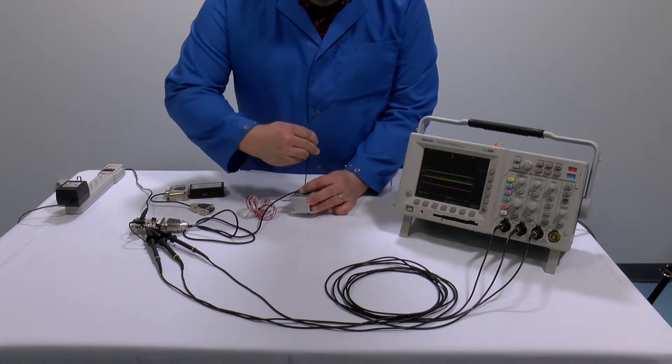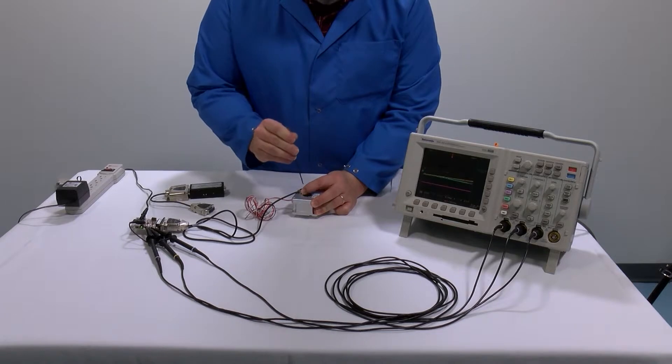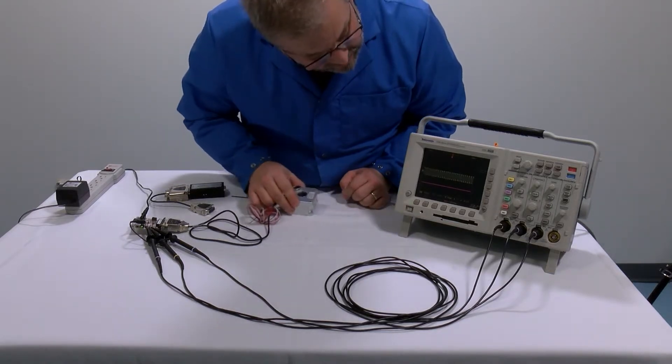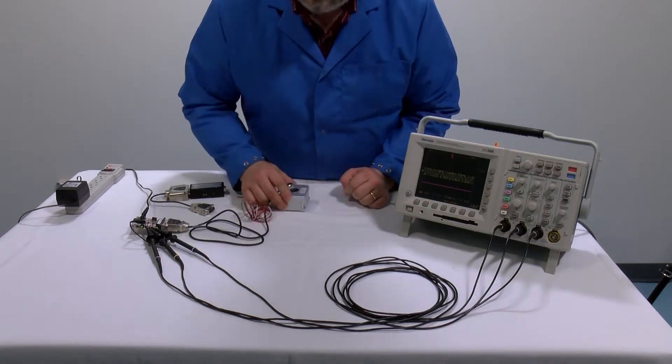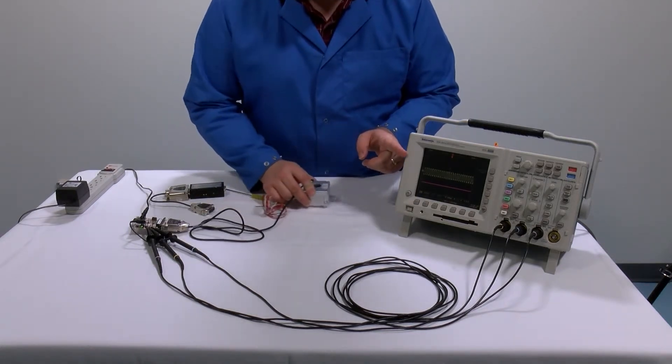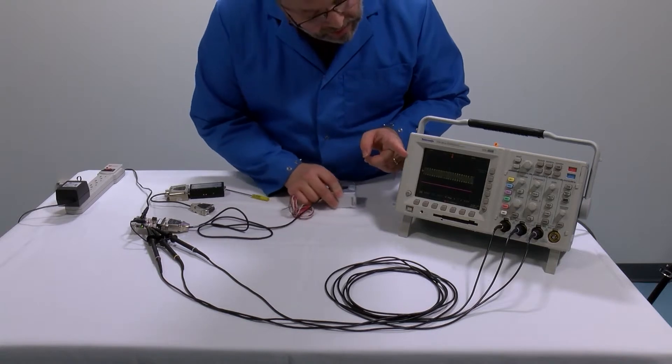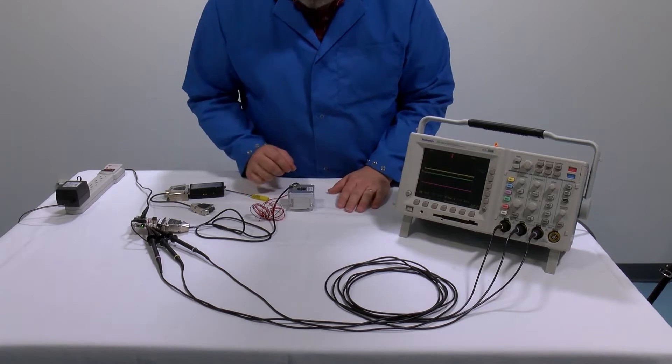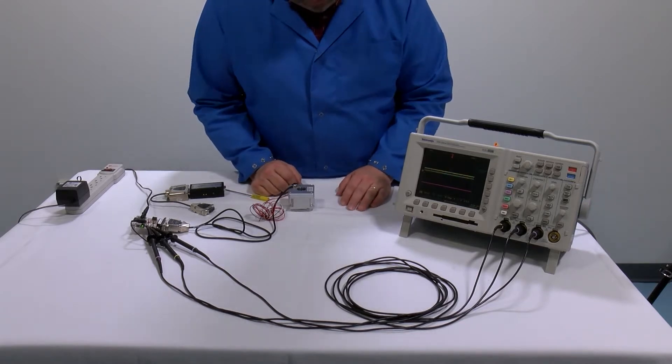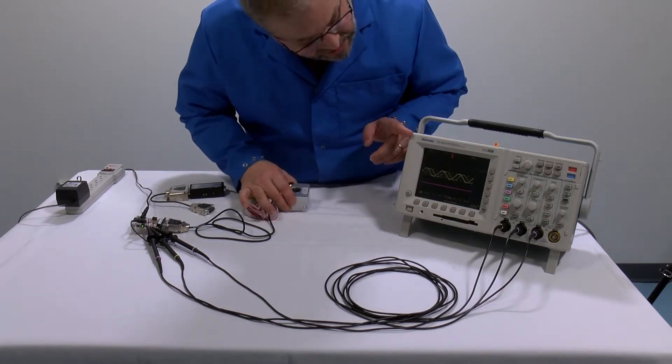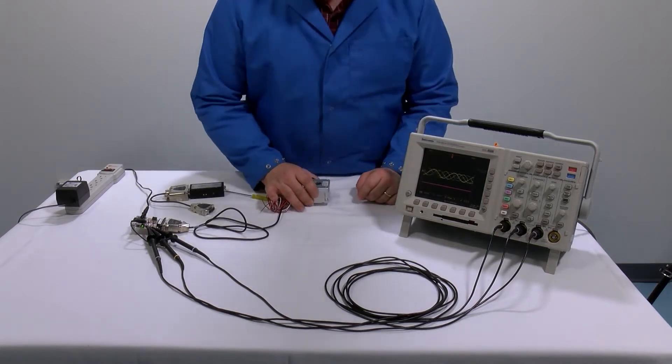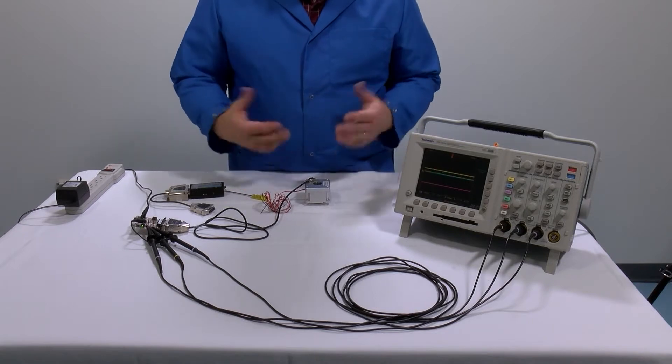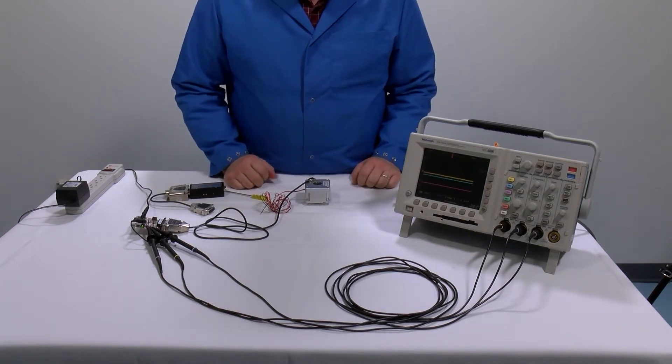So for the sake of argument we've gotten our assembly and we're not getting an index trigger. Hopefully you can see that on the scope. I'm spinning more than 360 degrees and the index pulse never triggers. We are getting sine and cosine which is on the order of around 800 millivolts peak to peak which is good, that is within spec, but the fact that we don't have an index window is bad.